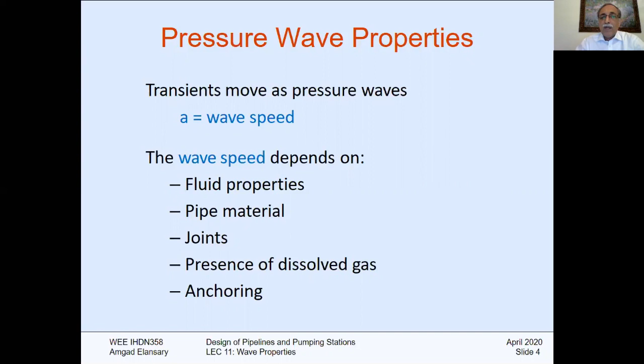The wave speed depends on several parameters. One, fluid properties like density, bulk modulus, and any other things related to the fluid property. Pipe material, like steel or PVC, the kind of material it is made from. Joints, like flexible joints, for example. Presence of dissolved gas; if there is a lot of gas or gas bubbles there, this is very important. And anchoring, the kind of support. This is more or less the important elements that affect the wave speed.